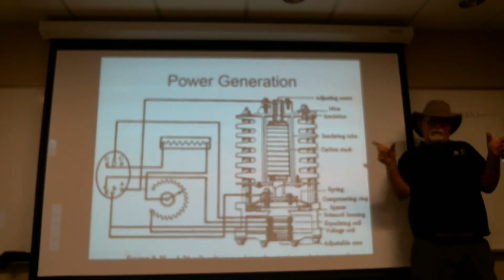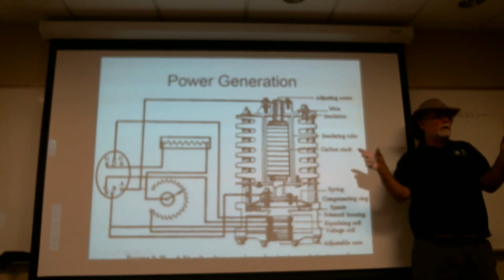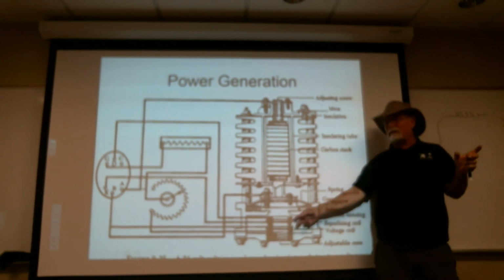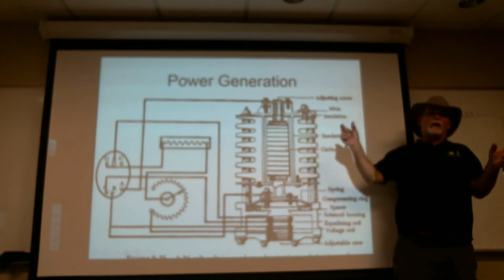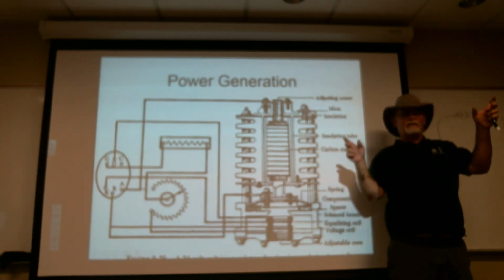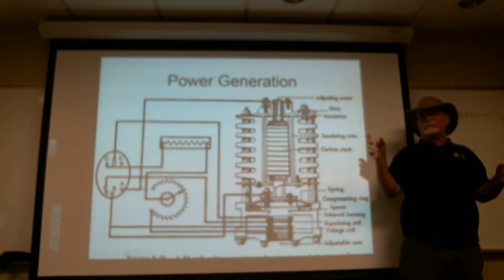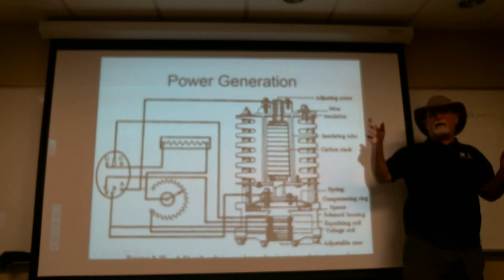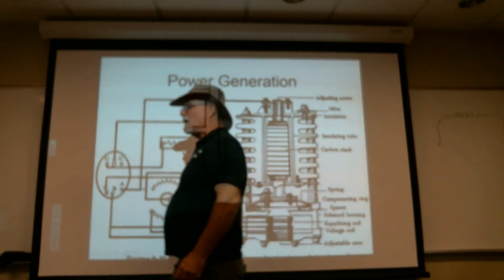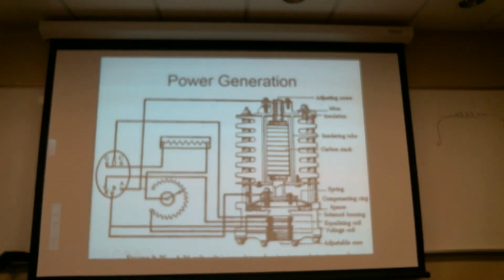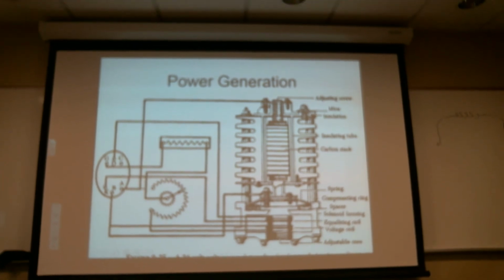I'm going to wire these things in a mirrored manner so that while one generator's equalizing coil is turning it higher, the other generator's equalizing coil is backing it off. So the two regulators behave opposite of each other. However, to do that, I have to introduce a very small voltage drop in the output of the generator, either on the positive side or the negative side of the armature.